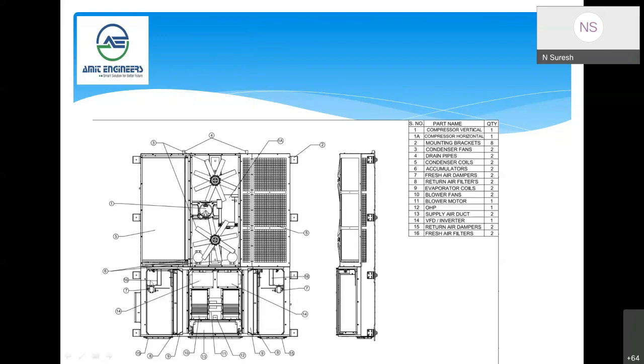say, for example, the ambient temperature is very low, and the fixed speed compressor is running. To avoid any liquid flooding, the accumulator is designed in such a way that the refrigerant which comes from the evaporator goes to the bottom, and there is a tube from the top. Only vapor will go into the compressor system, since the compressor is designed only to compress vapor. That is why there should not be any liquid flooding inside the compressor. So this is very important. Even proper maintenance will avoid any liquid flooding into the system.